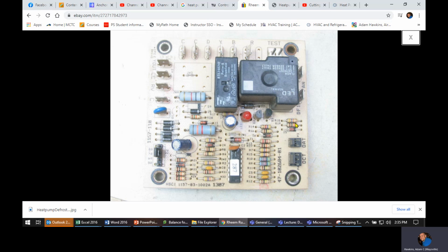Now there's something that has to happen in order for it to be forced in. So on this one, you see it's got an outdoor coil temperature sensor, OCT, and an OAT, outdoor air temp or outdoor ambient temp. May or may not always have both of those, or they could look very different, but that's what those are. Over here is your timer. So this one is 90, 70, 60, 50. A lot of them are 30, 60, 90. And you're just going to set that on the combination that you want to give it its time, however long you want it between checks.